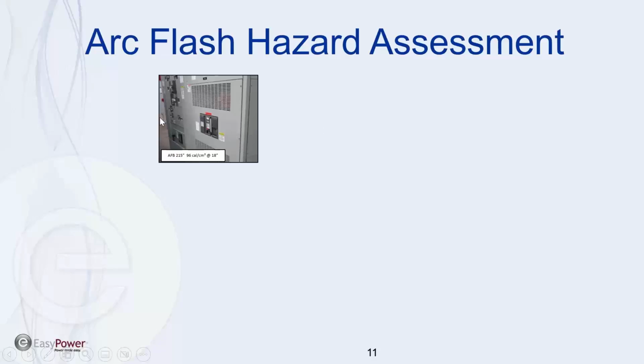Thing is, the transformer outside is still a 5,000 kVA transformer. And it's still from the 60s. So it's got low impedance and causes high arc flash levels. So in this case, we have 96 calories at this point. If an arc flash were to occur, it would be catastrophic and it would cause a problem.